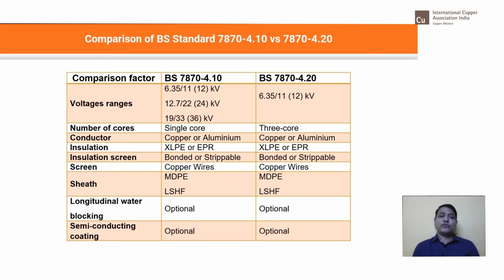7870-4.10 is for single core cables, copper or aluminum, and 7870-4.20 is three core cables. When it comes to 4.10, there are three voltage grades covered, and they are all single core. When it comes to 4.20, they are three core cables and only one voltage grade, that is 11 kV or 12 kV. Otherwise, as you can see from the design, they are unarmored cables.